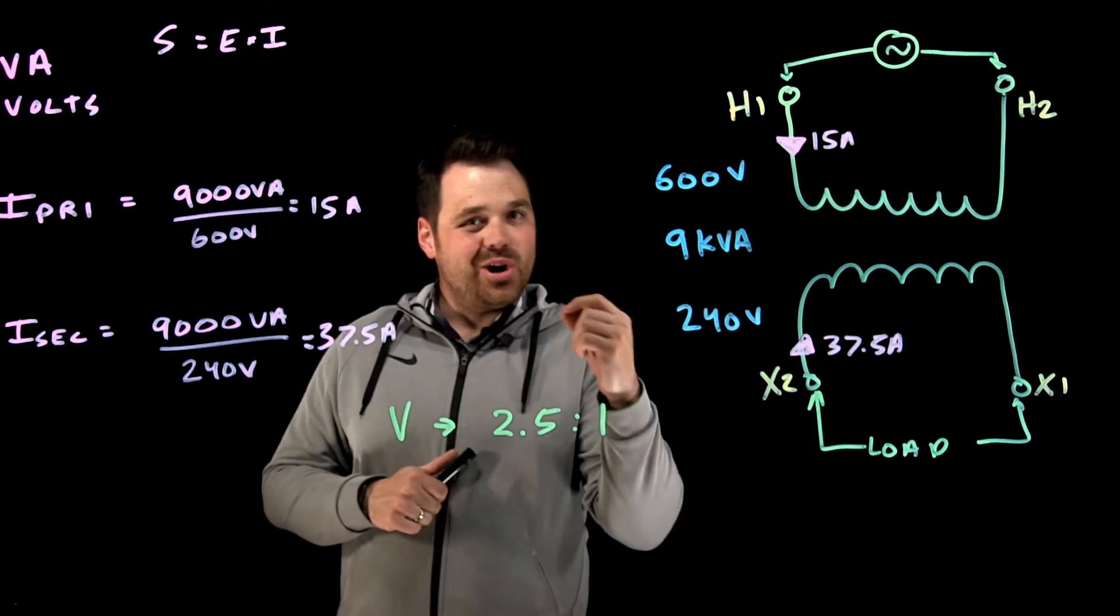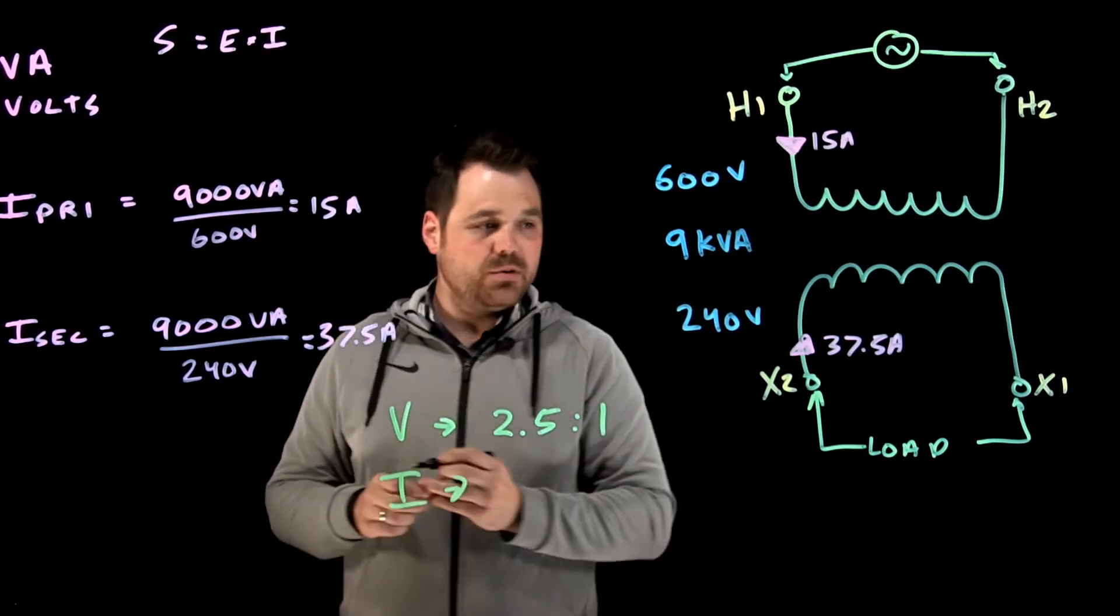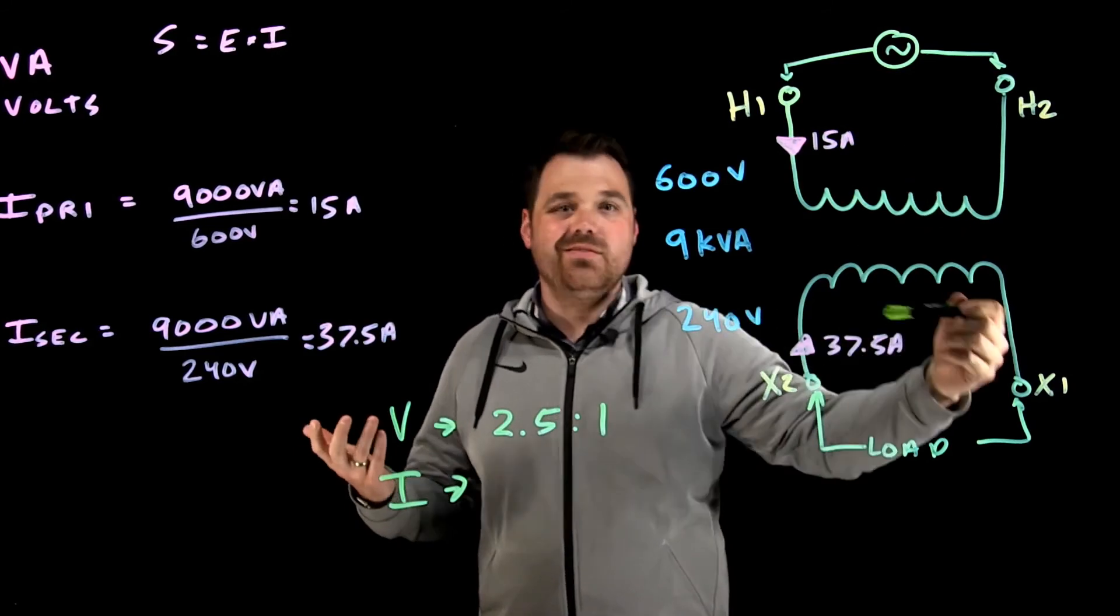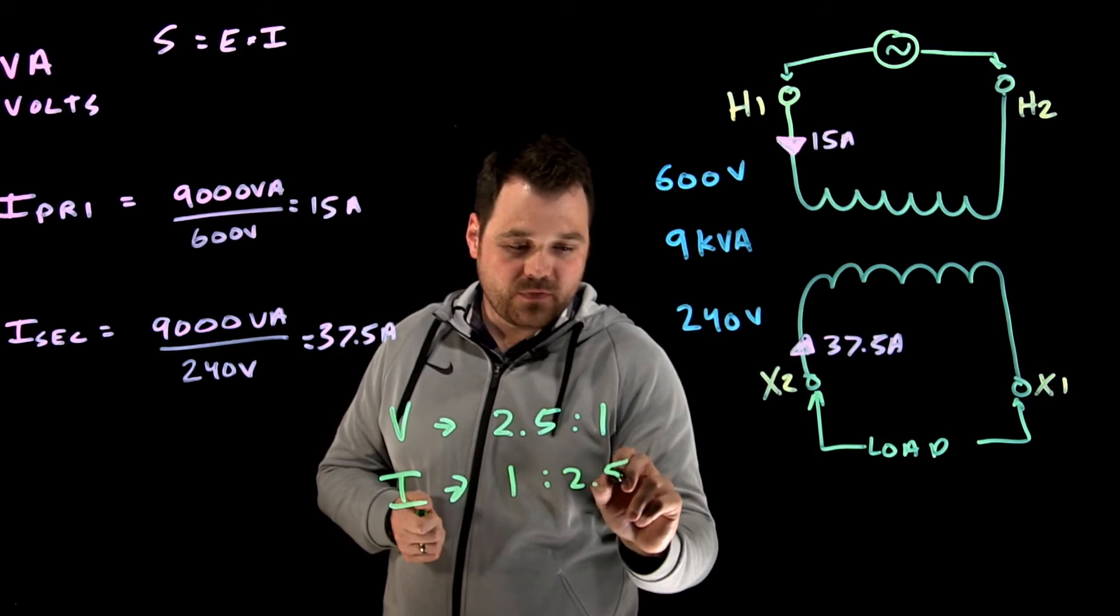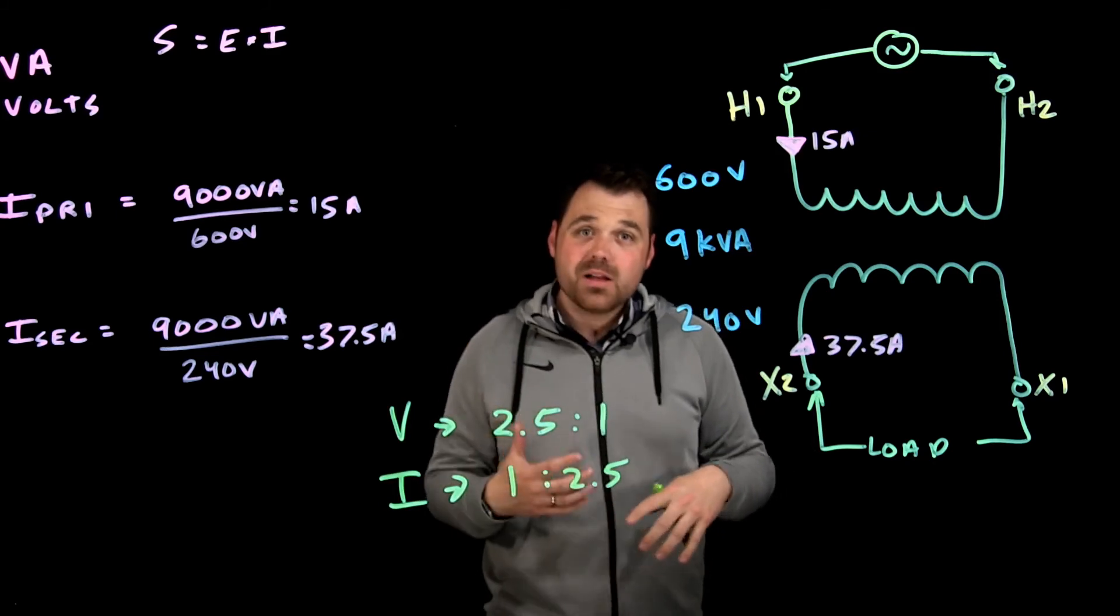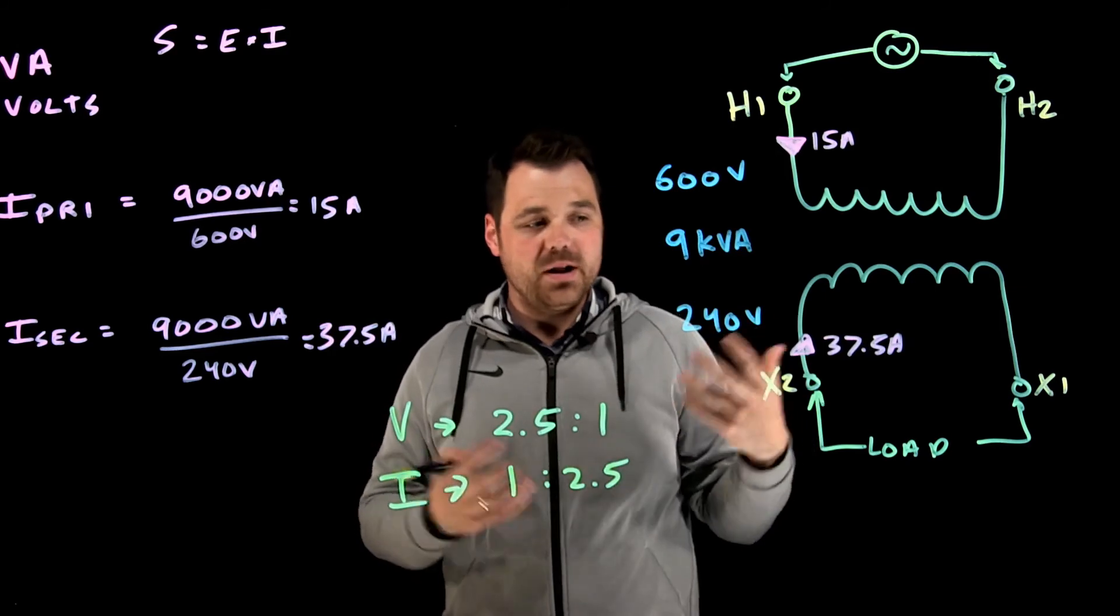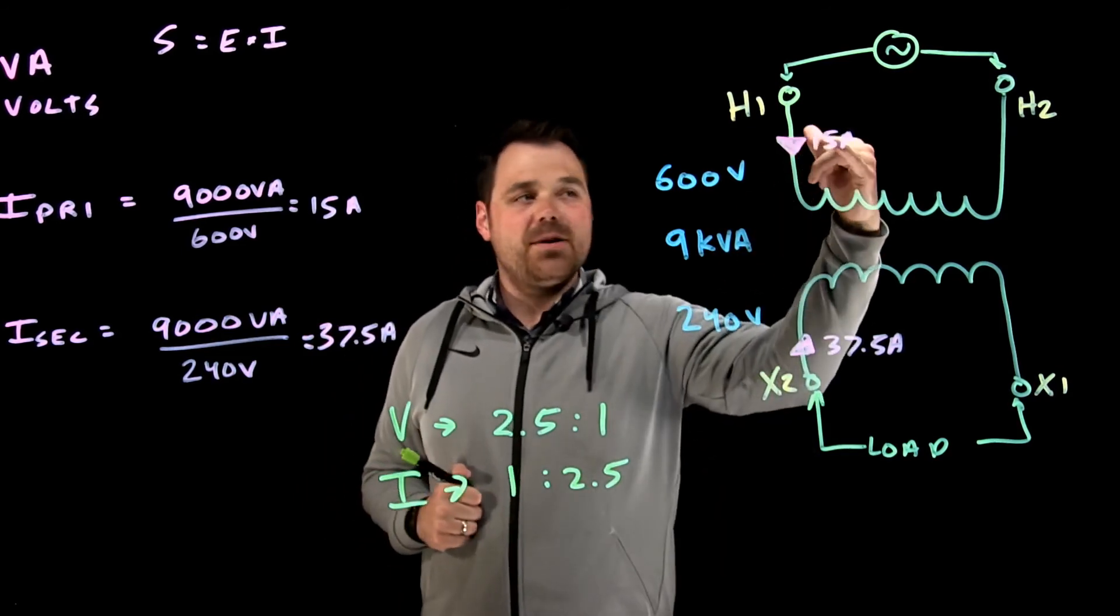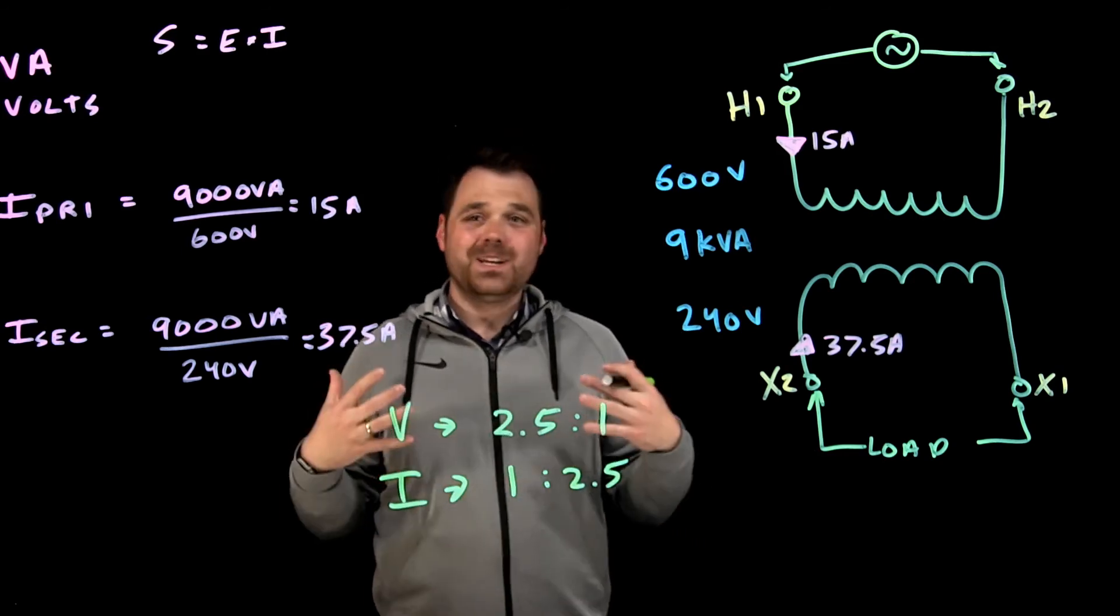My current ratio should always be the opposite of that. In this case, my current ratio, I would go 37.5 divided by 15 or 15 divided by 37.5, which gives me a 1 to 2.5 ratio. Those two ratios matching up like that, we discussed in another video. But you'll see your current and voltage ratios are actually opposite. When I go 37.5 times 240, I get my 9,000 VA. Same up here. 15 amps times 600 volts gives me my 9,000 VA.